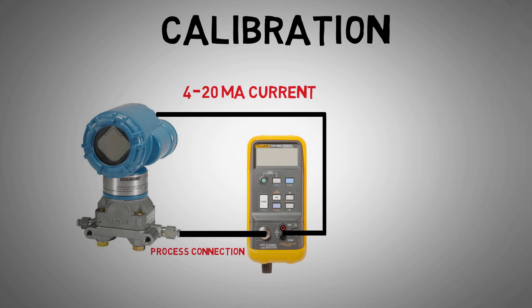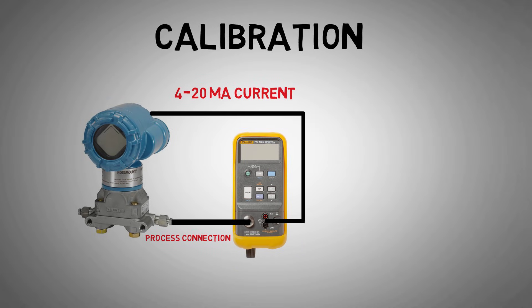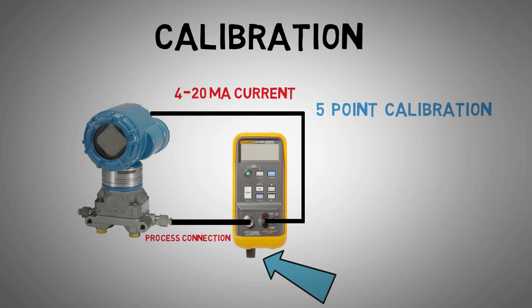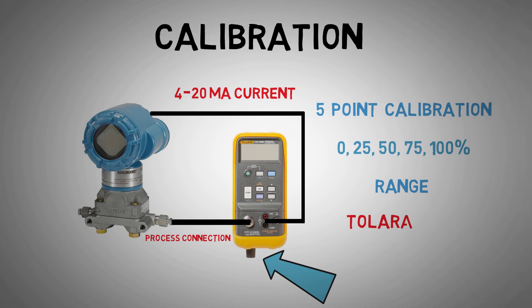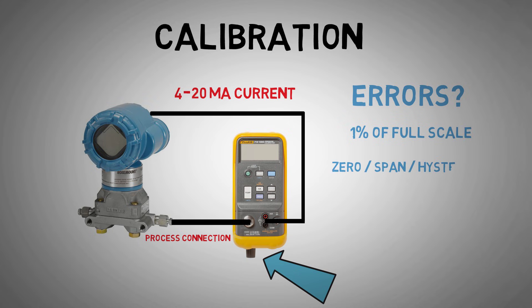This is what the control system is converting to a reading for our process operator. We would then apply various test pressures along the range of the transmitter and record the values on a calibration certificate. In a 5-point calibration, we will often be testing 0, 25, 50, 75 and 100% of the range of our transmitter. We would work out if the transmitter is within the required accuracy — something like 1% of range maximum error is usual for general purpose pressure transmitters. We would also check for zero, span and hysteresis errors.